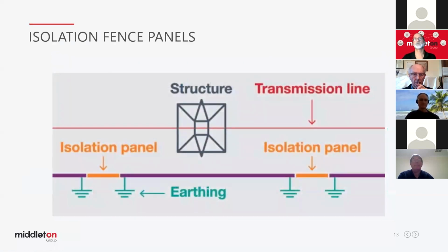The second slide here just shows if we've got an HV structure, we could be talking 330 kV, 500 kV, 132. If there's a fault at that structure, again, we'll have an EPR. And that fence you can see in purple at the bottom there, if it was continuous, it would be picking up the voltage of the soil very close to that structure and transferring that voltage along its conductive length to a far off point where the soil voltage is a lot lower, and potentially a large voltage can be transferred out and create a non-complying hazard further away.